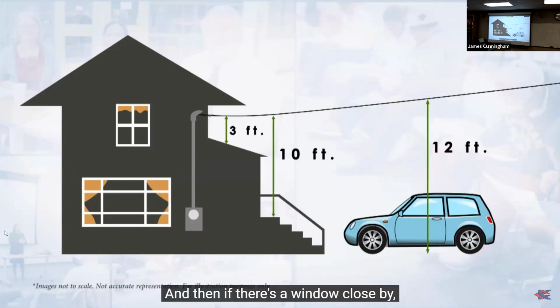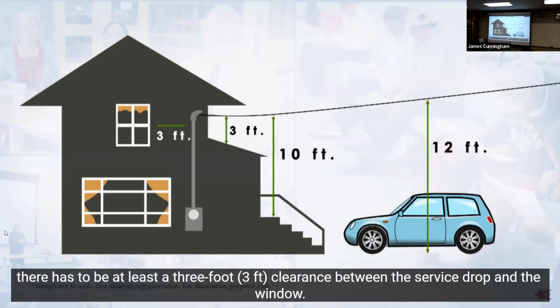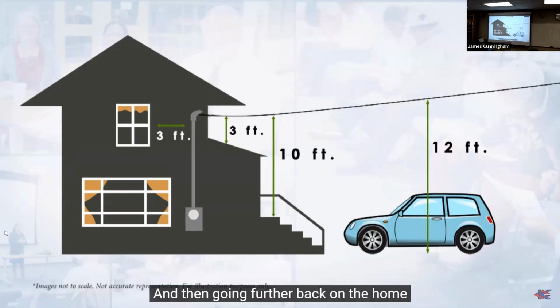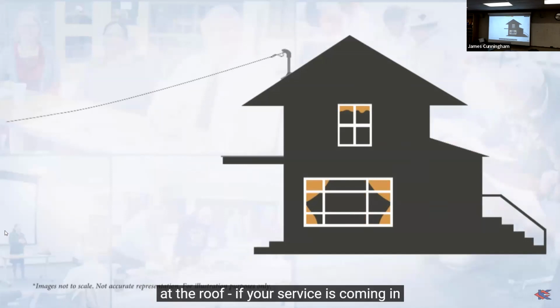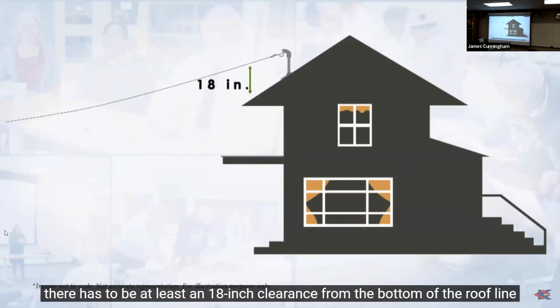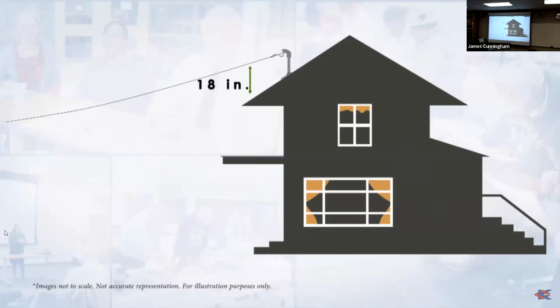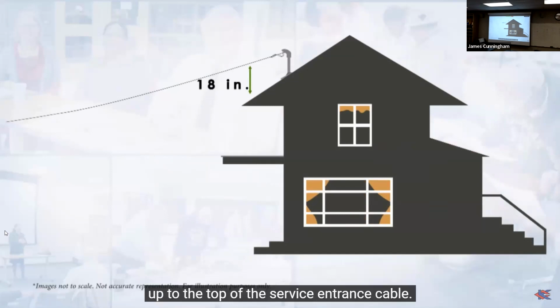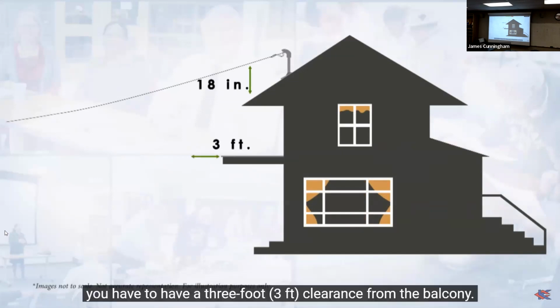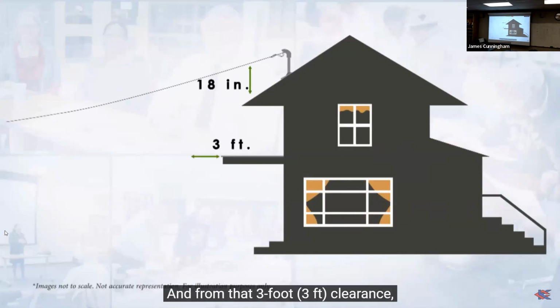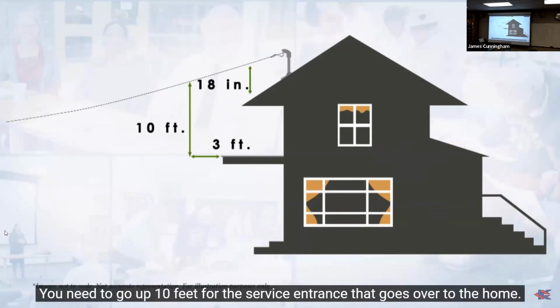And then if there's a window close by, there has to be at least a 3-foot clearance between the service drop and the window. And then going further back on the home, at the roof, if your service is coming in on the back of the home on the 2nd story, there has to be at least an 18-inch clearance from the bottom of the roof line up to the top of the service entrance cable. And if there's a balcony on the back of the home, you have to have a 3-foot clearance from the balcony, and from that 3-foot clearance, you need to go up 10 feet for the service entrance that goes over to the home. That clearance must be adhered to as it relates to the National Electric Code.